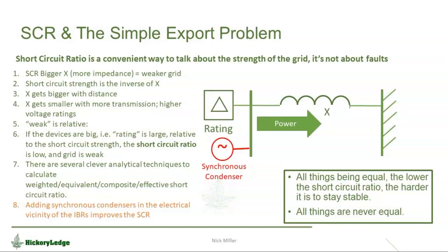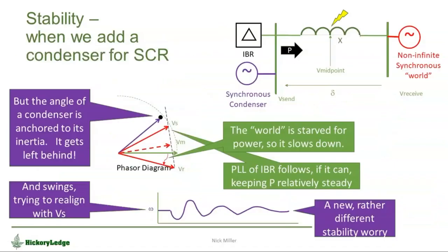But now I've introduced something that kind of looks like the synchronous machine. So now I've continued with my color coding. My infinite world is no longer infinite, that's red, but I've got a synchronous condenser which is done in purple here. I want to distinguish the two things. So now the phase lock loop tries to maintain the power export by chasing the sending end, the receiving end voltage, but the angle of the synchronous condenser can't move instantly. It's a state variable and it has inertia associated with it. So the synchronous condenser supports the bus, that's good.